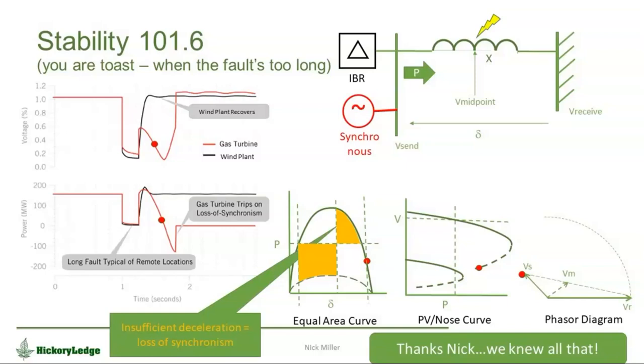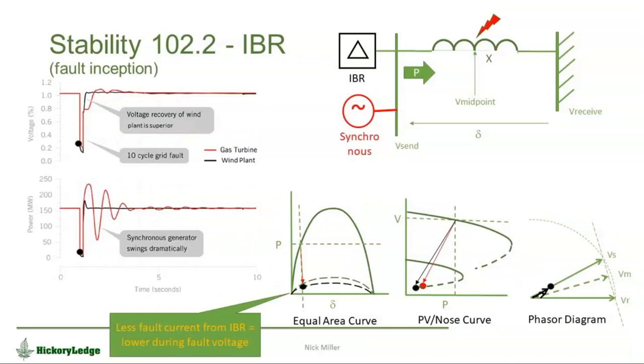On the other hand, now let's look at what happens with an inverter-based resource. This could be solar or wind. This is now back at the time of the fault inception. The pre-disturbance condition is the same. The voltage collapses during the fault. The voltage collapses further because the inverter-based resource doesn't deliver as much fault current. So the during-fault equal area curve is lower, as the black dots show. You're farther down the collapsed PV curve, and the situation is not good.